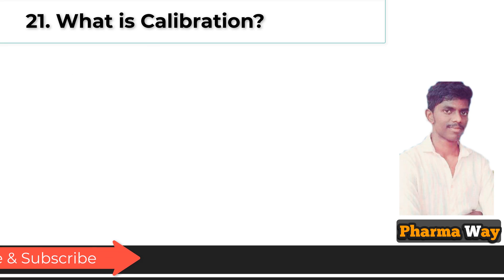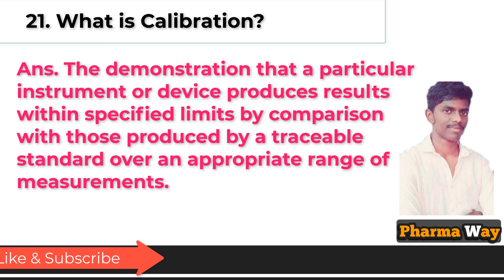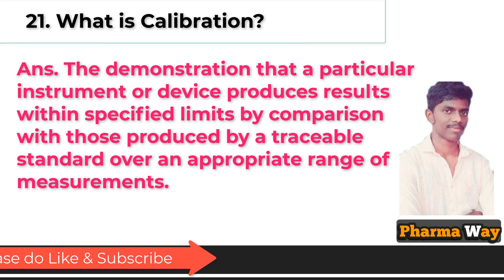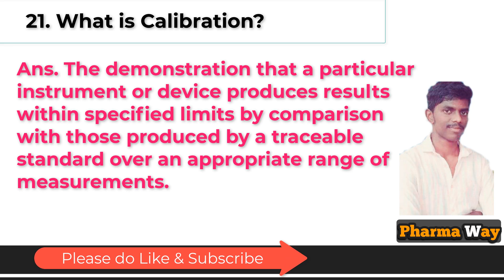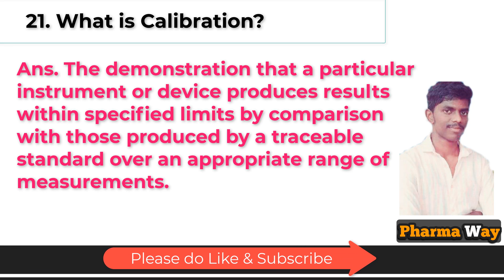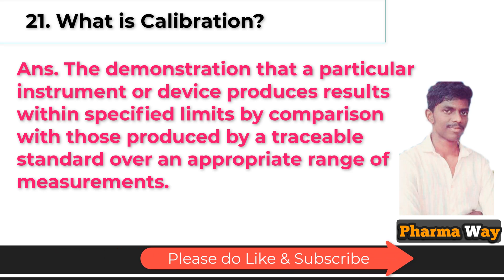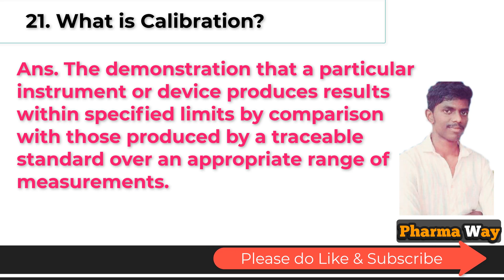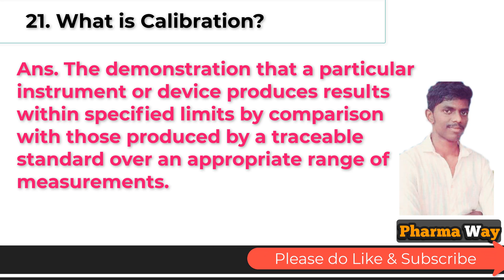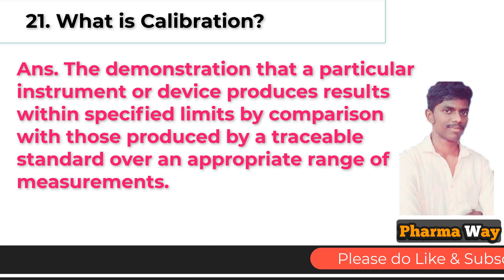What is calibration? Answer: It is the demonstration that a particular instrument or device produces results within specified limits by comparison with those produced by a traceable standard over an appropriate range of measurements.